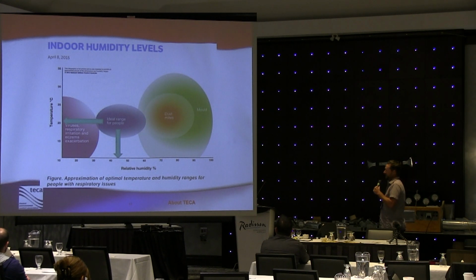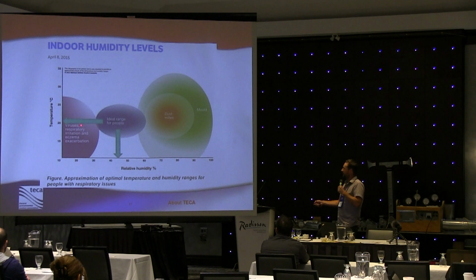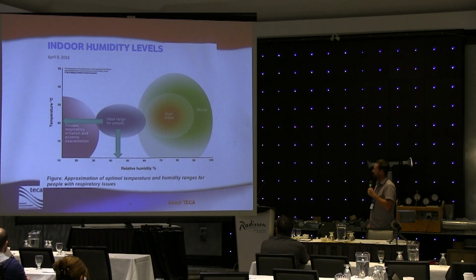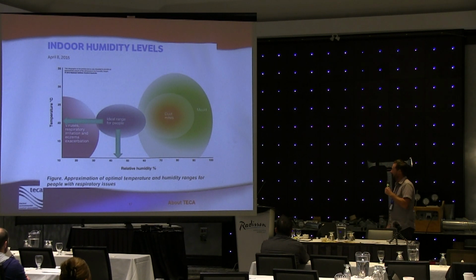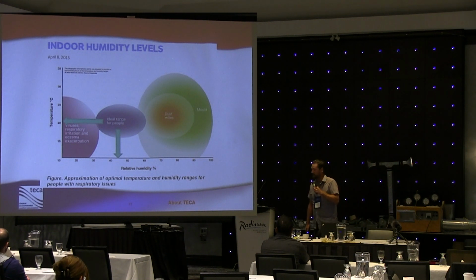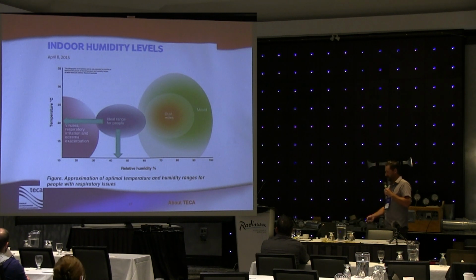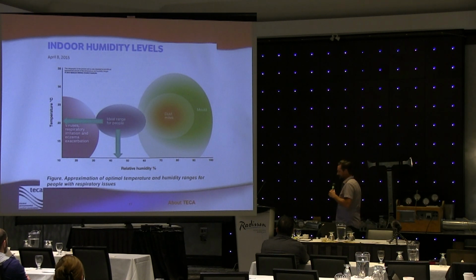If we get too dry, we run the risk of other uncomfortable situations for the occupants. Viruses tend to breed in dry, low humidity environments. We can get some respiratory irritation, eczema exacerbation, and the like. And then when we get into high humidity, we run the risk of mold and moisture buildup. It's also a breeding ground for dust mites, which a lot of people are very allergic to, so you have to watch for that. But this is our ideal range for people, somewhere in this area here. You probably already know that, but the ideal range for people is what we're targeting when we ventilate. We're trying to get rid of that excess humidity, and we're trying to maintain a comfortable indoor temperature.